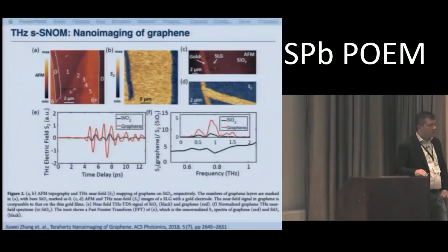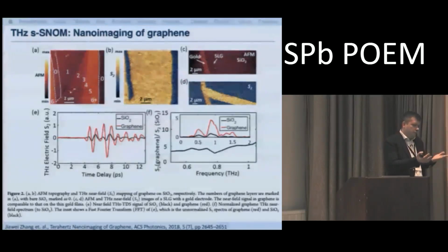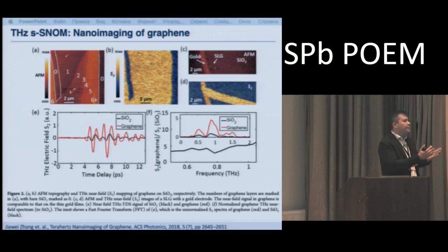And how can this resolution be enhanced? Well, actually, by using sharper probes, because the resolution depends on the probe sharpness. But once you have a sharper probe, you have to spend more time collecting enough signal at every point of the scan. So in principle, an infinitely sharp probe can be used if you have infinite time and zero drift of the system to collect all those images.